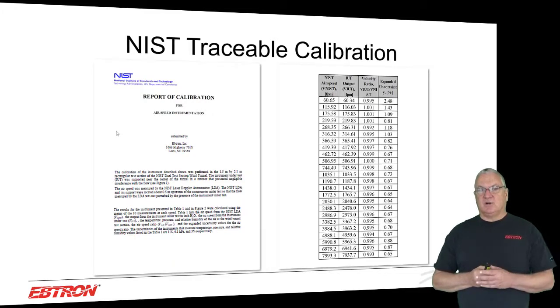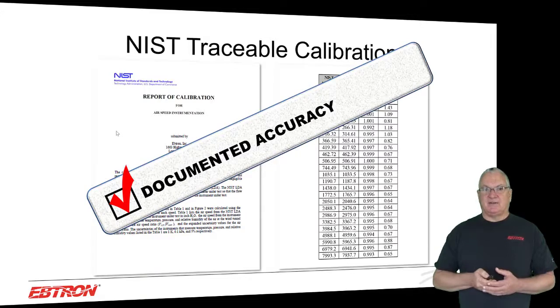If you take a look at this report of calibration, just quickly, the leftmost column there in the table is the NIST airspeed, which is based on a laser Doppler anemometer point measurement. And then the next column in is our reference, what it reads, the ratio between the two. So you see that our reference is within 0.5% or so of the NIST standard. And then the expanded uncertainty, which is nothing more than the standard deviations of the data set of the NIST readings and our readings, and that starts your traceability. And basically, it's documented accuracy.